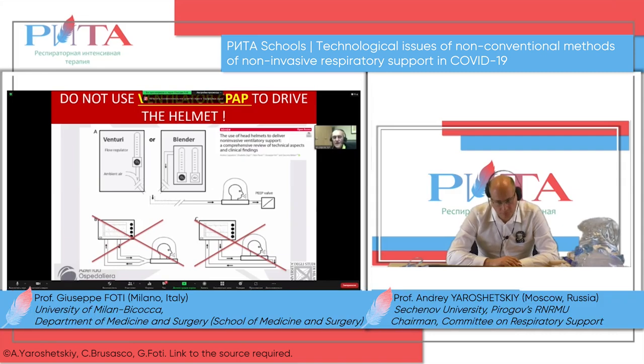The important point: you have to have continuous flow provided either by the Venturi, or by the mixer of the ICU, or by the ventilator going inside the helmet and then out to a PEEP valve, external PEEP valve, finish. Do not put the expiratory limb inside the ventilator. Do not use CPAP modality, otherwise the ventilator starts to think it has to provide a ventilatory modality, a CPAP, and so the logic of the ventilator is not to provide 60, 70, 80, 90 liters per minute, but just the flow needed to maintain a good CPAP.